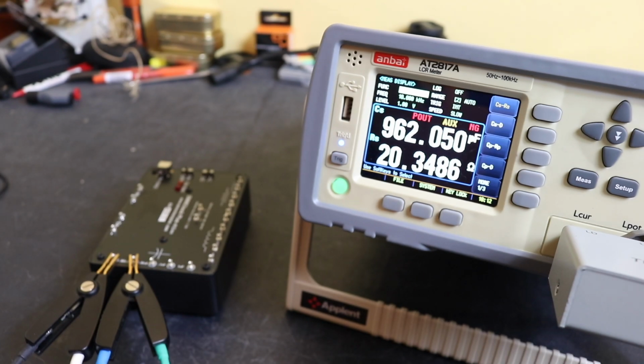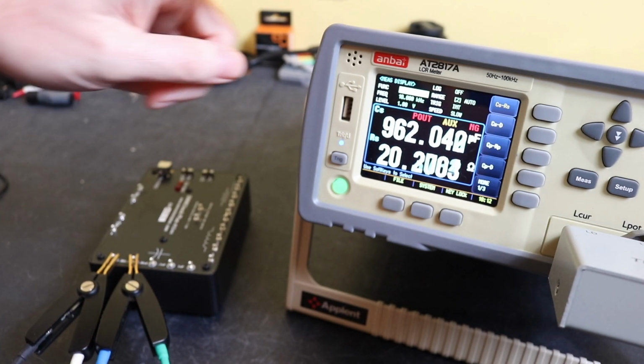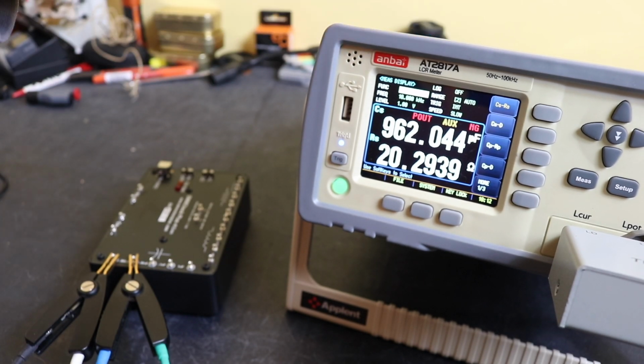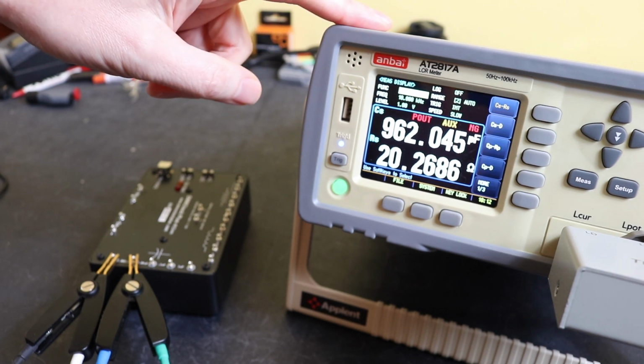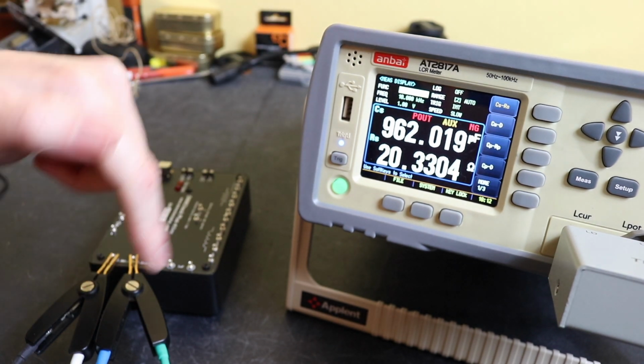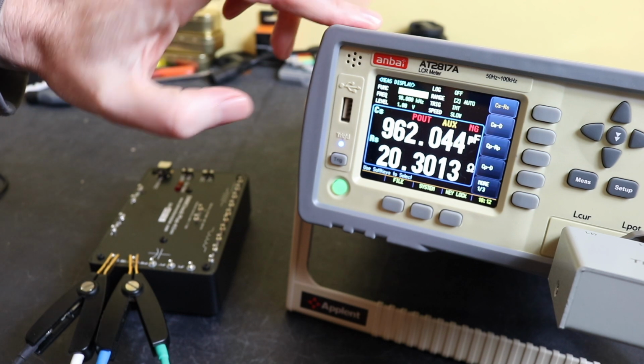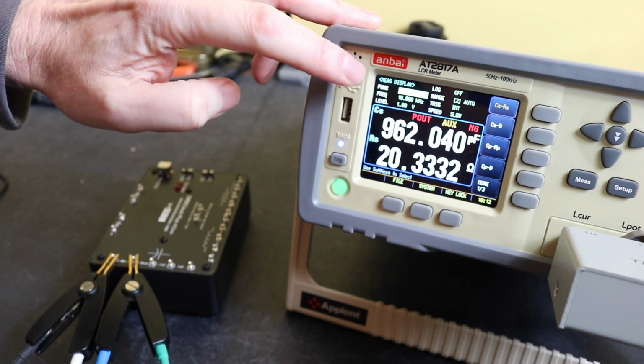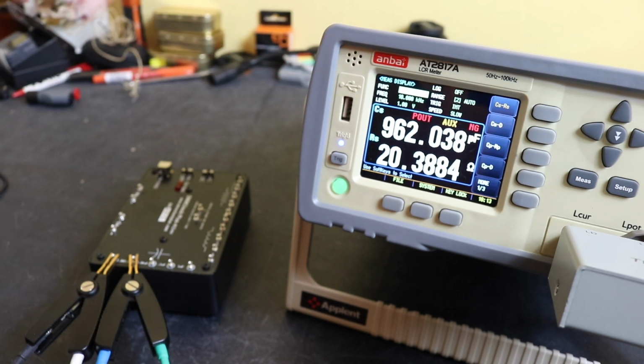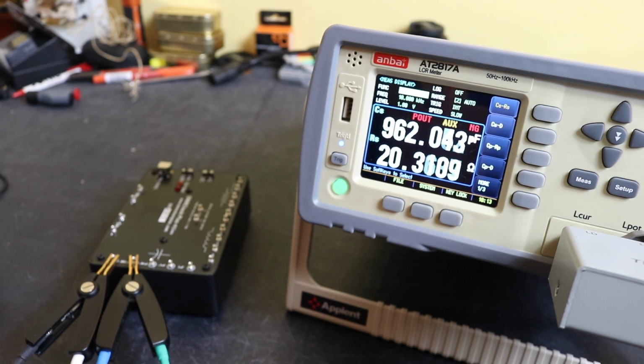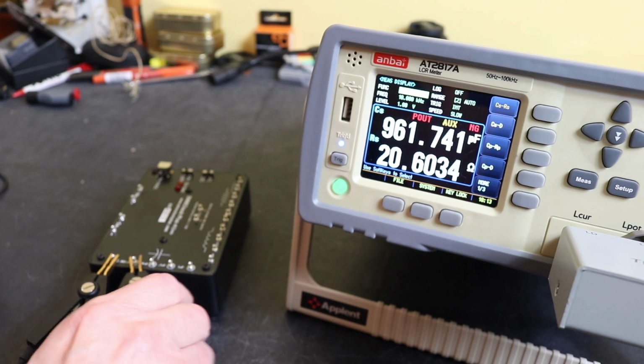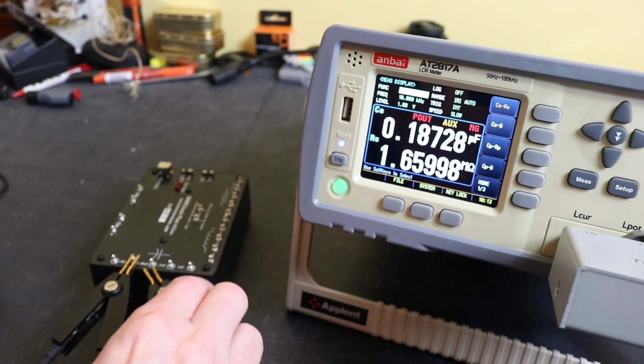Okay, so we are hooked up to our LCR meter, the AT2817A. I have also run corrections on this, open circuit and short circuit on the terminals, and I've set this to serial capacitance measurement at 10 kilohertz. 10 kilohertz is the test frequency specified on the calibration cert that comes with the DMMCheck Plus. On our first capacitance there should be 1 nanofarad, and we are at 962 picofarads. So we'll move along.